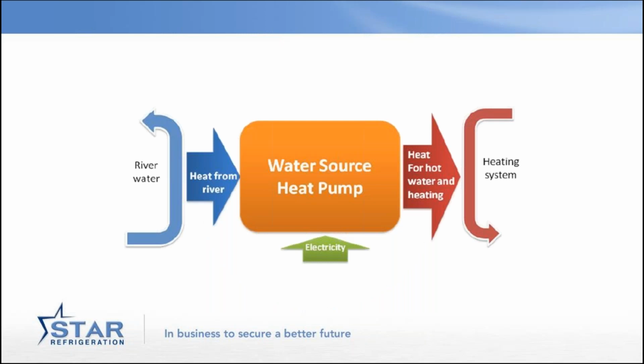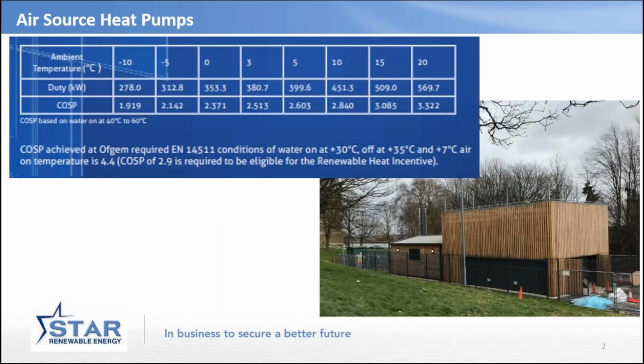So back to the river source heat pump, and that's largely what we've been doing in the country. And we've supported Vital Energy and West Dunbartonshire Council to deploy the UK's largest high temperature water source heat pumps in Clydebank. They're about 80 degrees delivery temperature, but also over 5 MW. We've also done a large air source heat pump. This is for Glasgow Housing Association in Glasgow, and it's doing about 400 kilowatts.